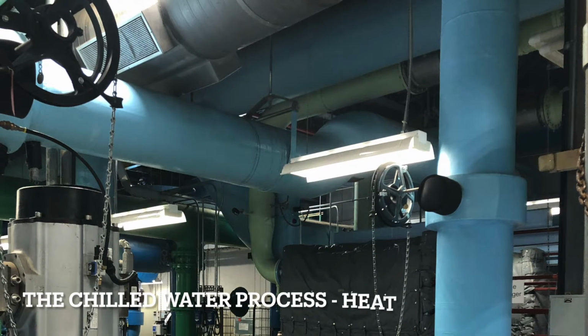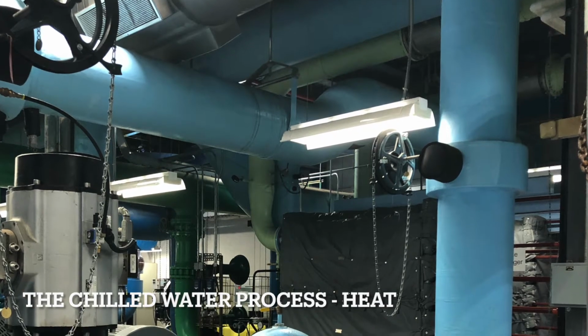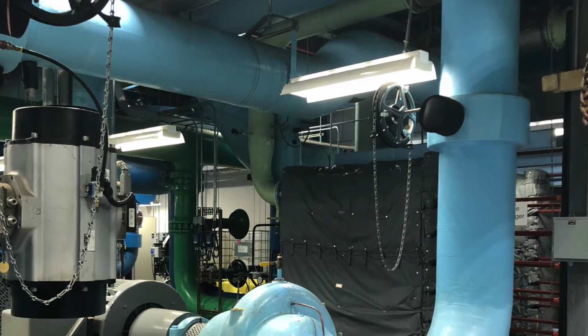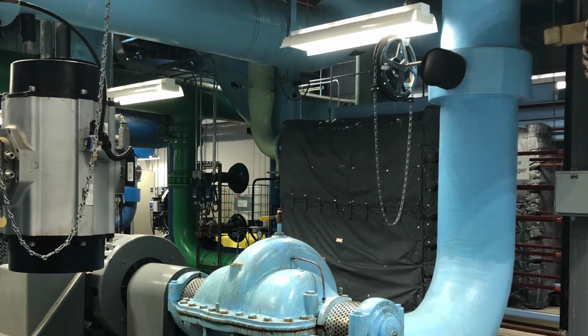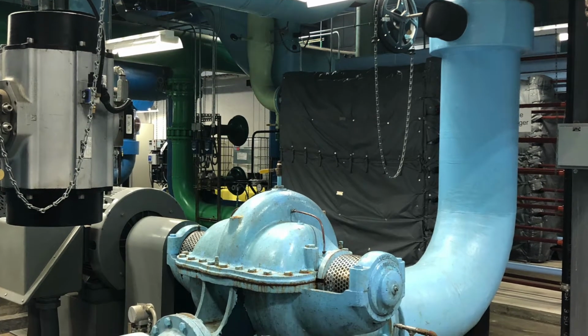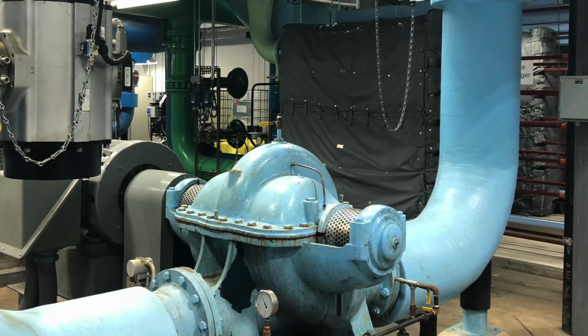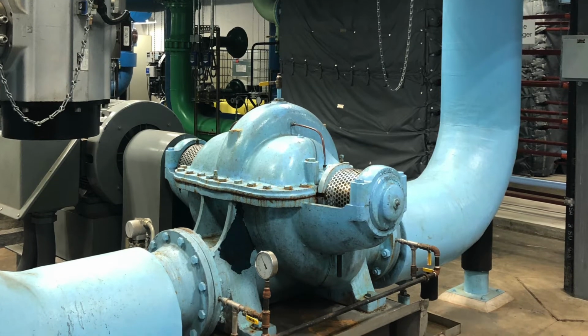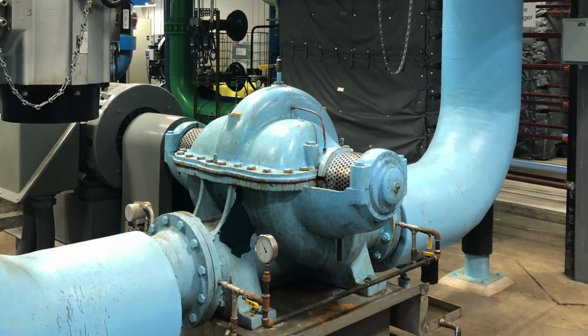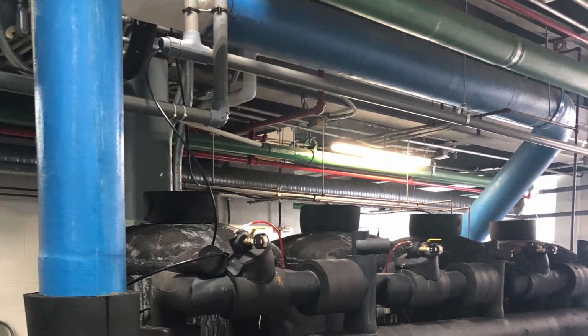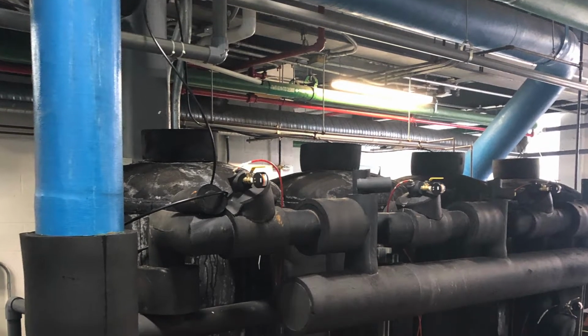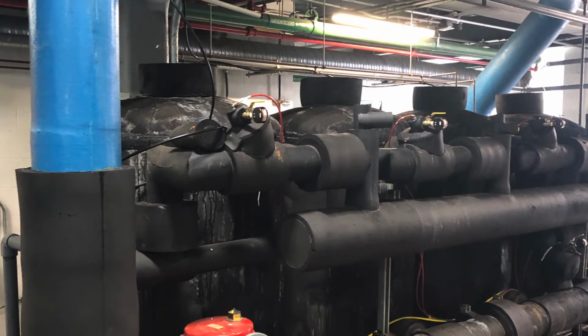The whole process of the chilled water system is a movement of heat. Heat is taken from the buildings on campus and put into the chilled water. That heated up chilled water is brought back to the chilled water plant, and a transfer of heat takes place between the returned chilled water and the refrigerant in the evaporator in the chiller. From there, another transfer of heat takes place between the refrigerant and the condenser water found in the condenser in the chiller. The newly heated condenser water is taken up to the cooling tower and is sent out into the air through evaporation.